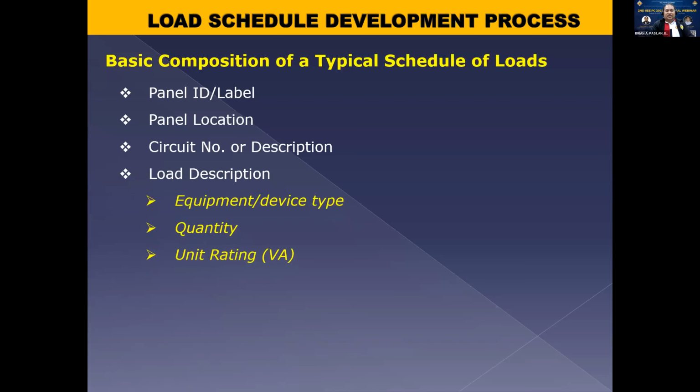Okay. And then the unit rating in power in terms of VA or kVA. So ito yung pinagbago kasi previously may mga designs na ang ginamit nilang unit sa power is watts or kilowatts. So ngayon pinagkuha na talaga na dapat in terms of VA. So na-account na yan yung power factor natin. Dapat i-convert na natin kung kilowatt yung nasa nameplate, i-convert mo na to VA or kVA para standardize na yung units natin sa load schedule.